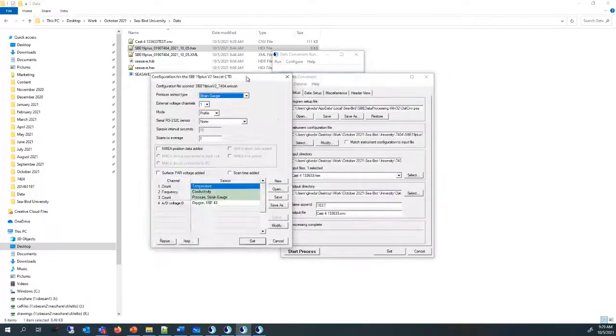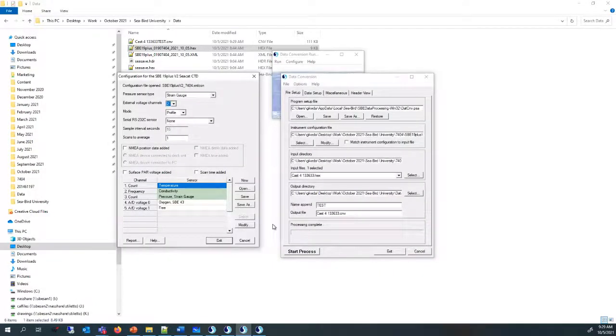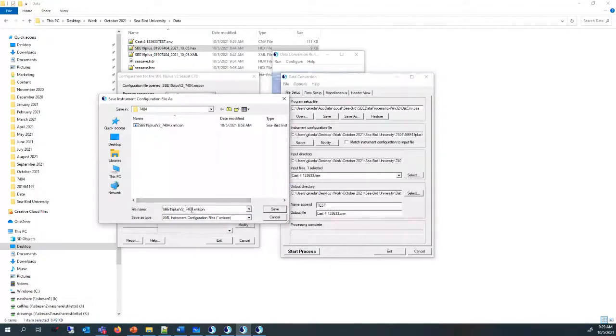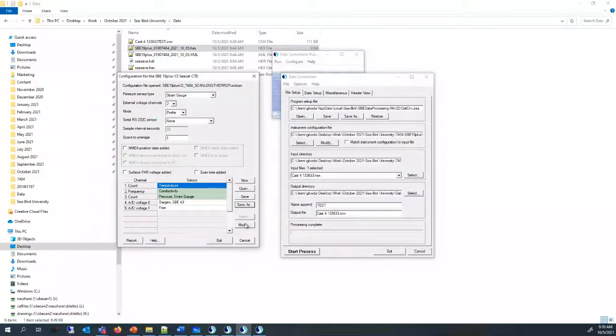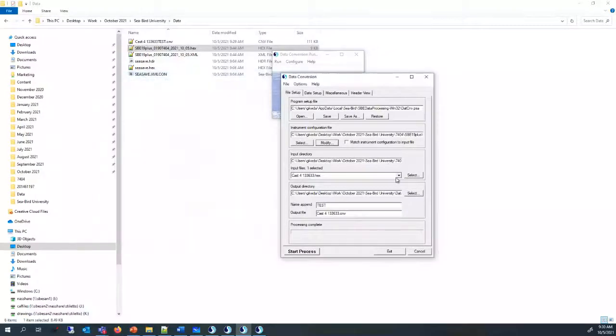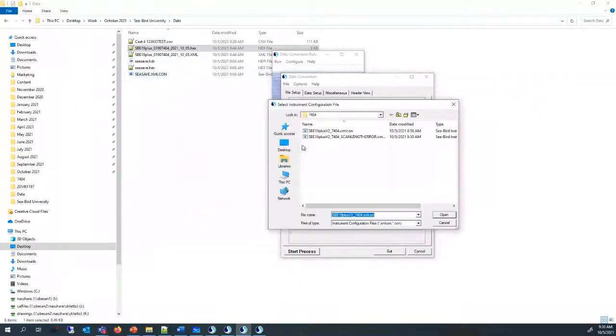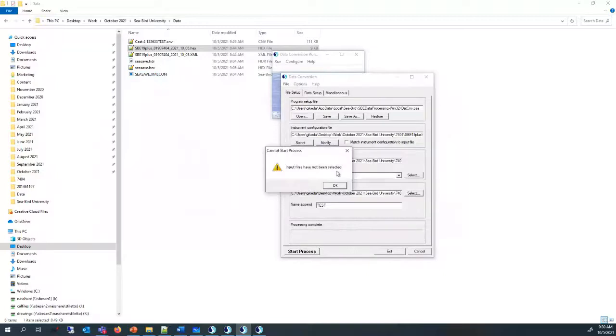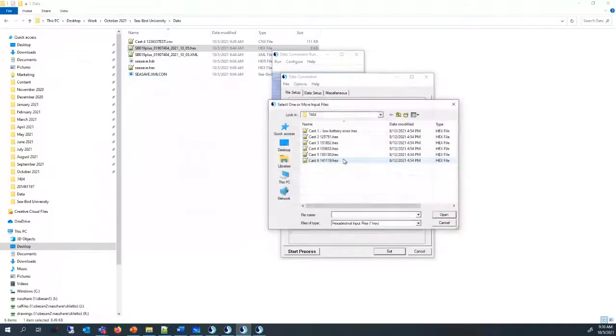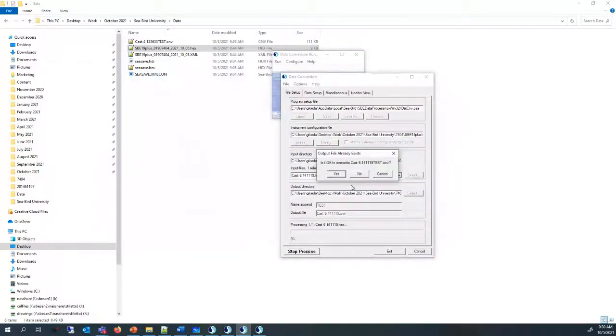The best way to do this is to click on your .con file, double check which sensors you have enabled on there, and also talk to your instrument with the DS command. So if you have 3 voltages enabled and you only have 2 voltages on your con file, that is typically a cause of this problem with the hex file. If you're a little bit more of an advanced user, one thing you can also do is look in the manual, where your temperature, your pressure, and your conductivity each have a number of characters. You can count all the strings and figure out where you are in that as well.